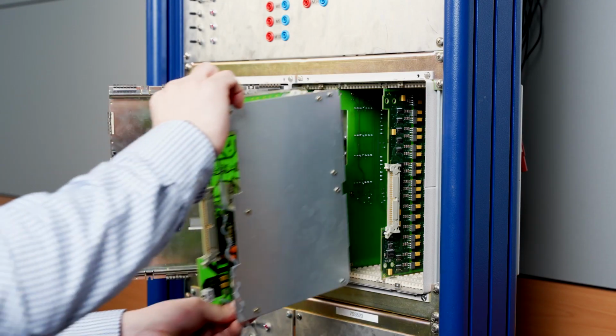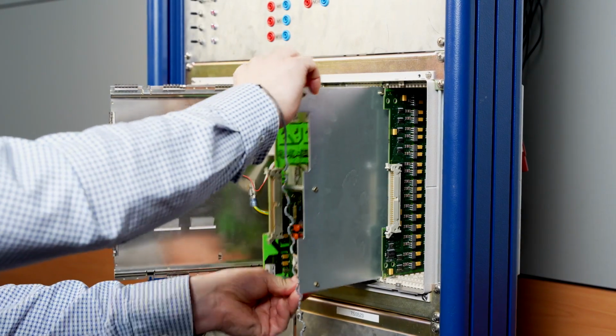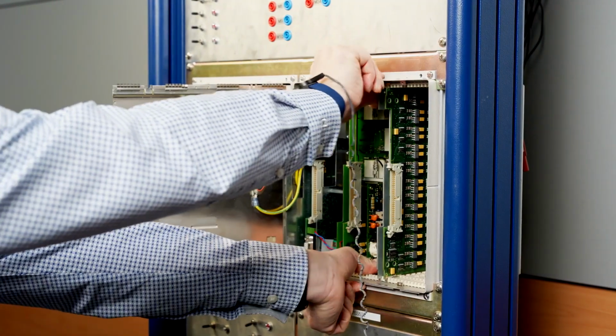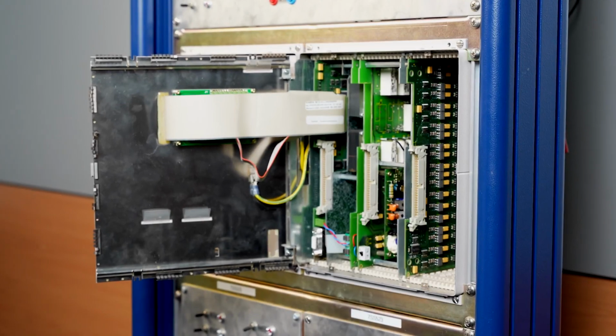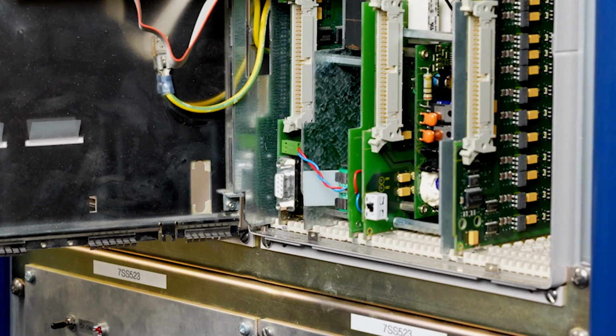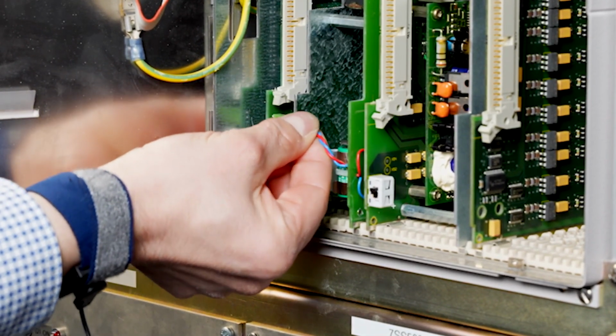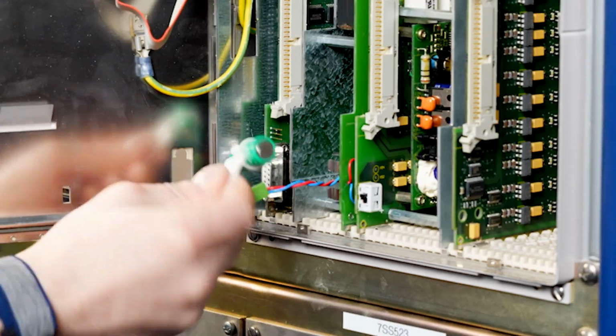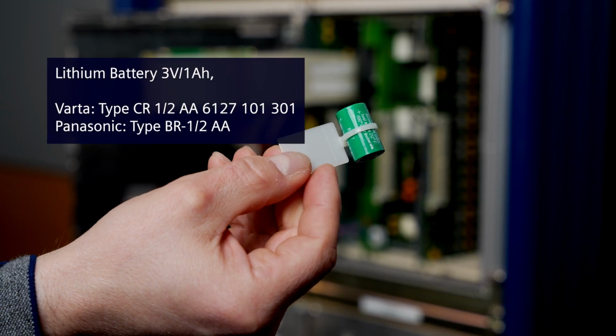Install the new assembly and replace the battery. Reassembling has to be done in reverse order and begins with plugging in the new assembly. When changing modules, we always recommend replacing the buffer battery on the processor module. To do this, loosen the battery cable from the plug and pull the battery out of the holder. We recommend one of the displayed battery types as a replacement battery.